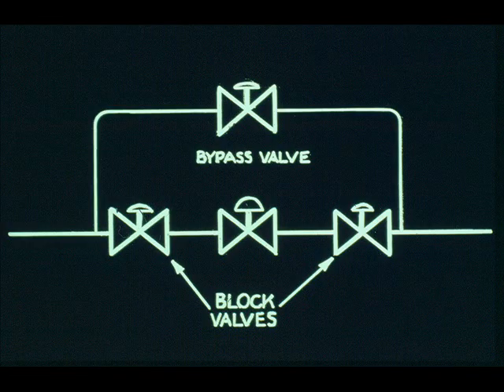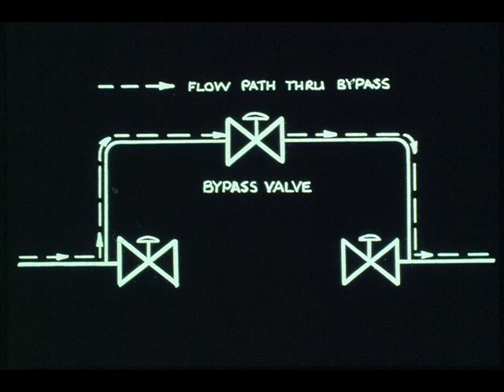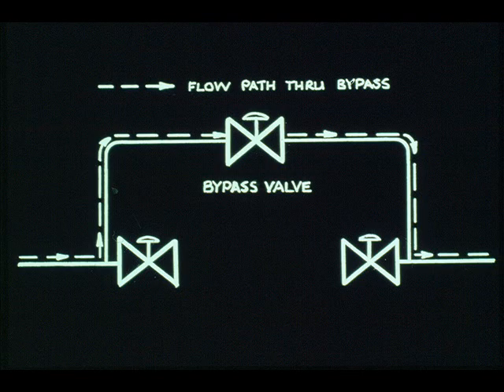Section 3.4 states that block and bypass valves shall be provided for all control and safety shutdown valves in accordance with Table 2. Table 2 covers the block valve and bypass valve size for a given mainline size. The function of the block and bypass valves is to permit removal of the control valve for maintenance without shutting down the unit.